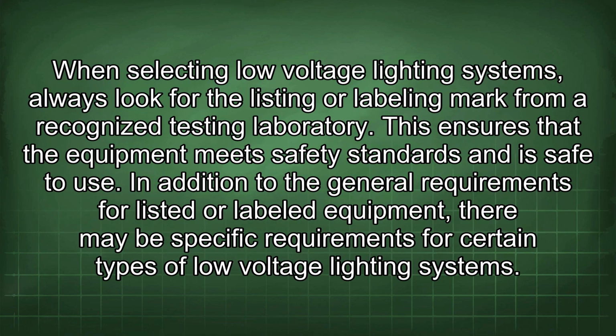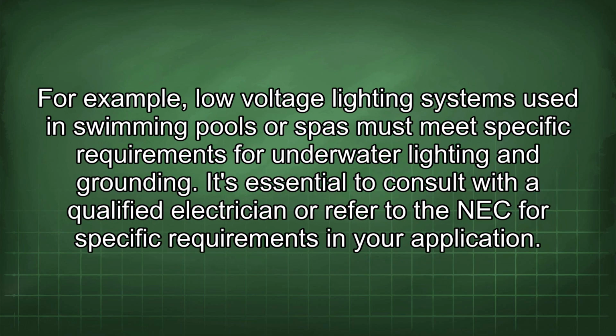When selecting low-voltage lighting systems, always look for the listing or labeling mark from a recognized testing laboratory. This ensures that the equipment meets safety standards and is safe to use. In addition to the general requirements for listed or labeled equipment, there may be specific requirements for certain types of low-voltage lighting systems. For example, low-voltage lighting systems used in swimming pools or spas must meet specific requirements for underwater lighting and grounding. It's essential to consult with a qualified electrician or refer to the NEC for specific requirements in your application.